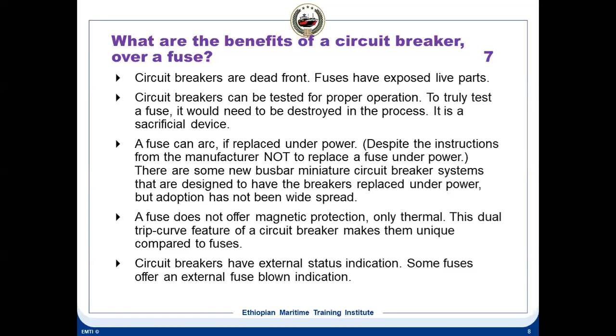A blown fuse can easily be replaced with a wrong size or even a jerry-rig, creating a safety issue. So when it comes to this, suppose you have a fuse which is like 32 volt 15 amps fuse. Now, can you replace this fuse with a higher voltage but at the same current rating? Suppose you have a circuit, you have got, let's say, a 50 volt 10 amps fuse, and you want to replace that fuse, but you got a fuse now, let's say of 250 volt of 10 amps. So the voltage rating determines the amount of space or a gap left after the fuse is open, okay, and it's interrupted the flow of the current. So the higher the voltage rating, the larger the resulting gap will be where the fuse opens, and wider gap means lesser chance of sustaining an arc.